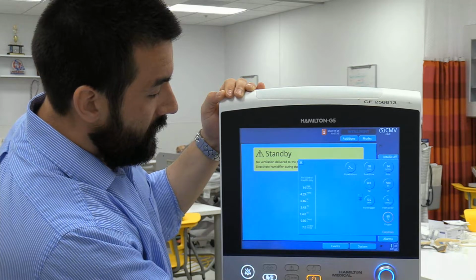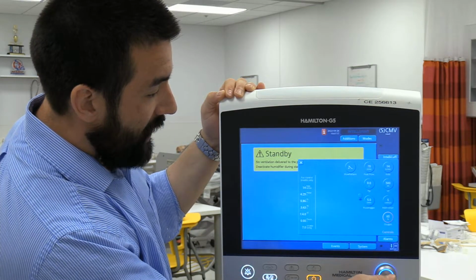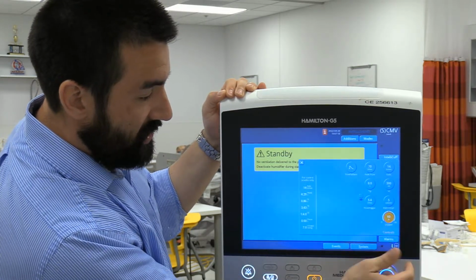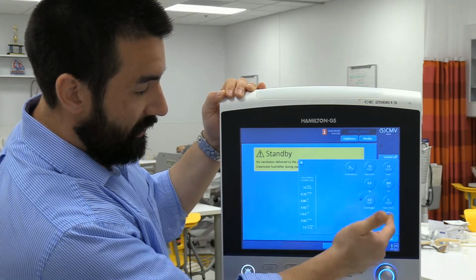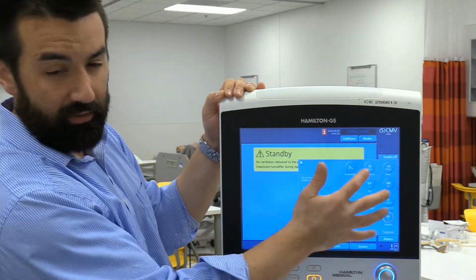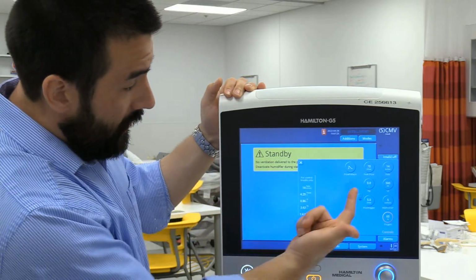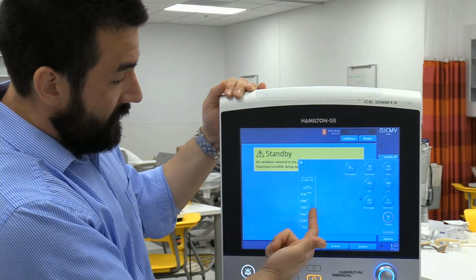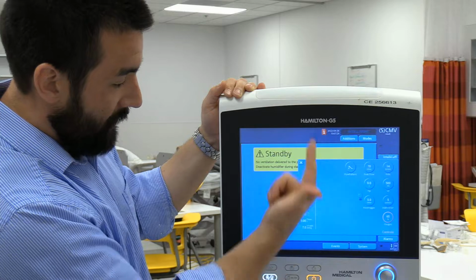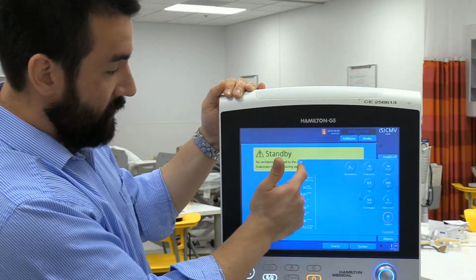All right. One thing I like to check, so our settings, to make any changes, you just touch, turn with the wheel, or you can touch. It is a pressure-sensitive touch screen, so if it's not going, you've got to hit it a little bit harder. All right, so all these settings are confirmed right here. Rate of 14, I time 0.86, got a good E time, 7 mils per kilo.